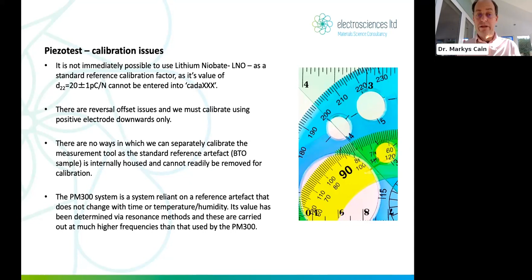Okay. So what do we use for calibration? First of all, we need to work out what we use for zero calibration, so zero piezo coefficient. Now, actually, this is really interesting. The manual says put something in that's got a piezoelectric coefficient of 0, like a bit of paper or a bit of PTFE or something like that.